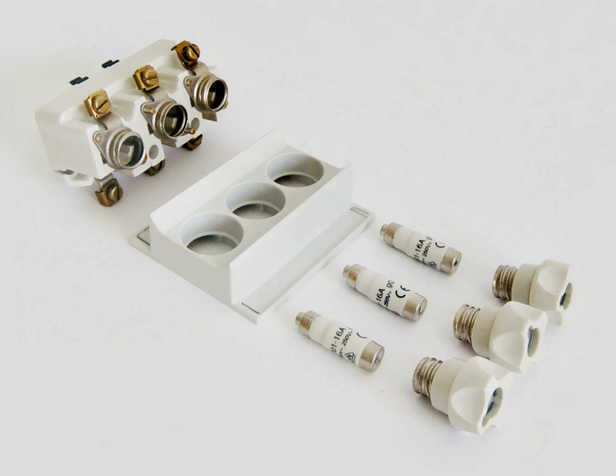Topic. British domestic fuses. In British residential installations, cylindrical fuses with a diameter of 1/4 inch and a length of 1 inch, 6.3 × 25.4 mm, in compliance with British standard BS 1362, are found inside a standard UK 13A plug. The specification calls for sand-filled fuses with a ceramic body and metallic contacts at the ends with a 5.5 mm length.